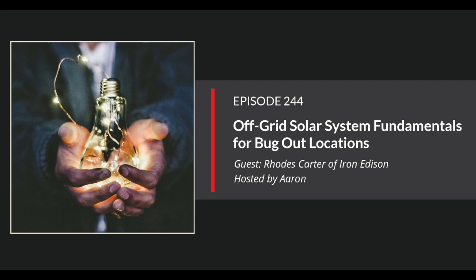So what winds up being the balance is to design a system that'll cover 80 to 90% of December and January, and have a generator in place, and just know that you're going to be running that generator maybe every 3 or 4 days for a few weeks around the winter solstice. And then the rest of the year, you still have plenty of generation. So no problem there at all. Plus, you may have a weather event that comes in where the sun doesn't shine for 3 or 4 days. So you need something to recharge the battery when the solar is not doing it.